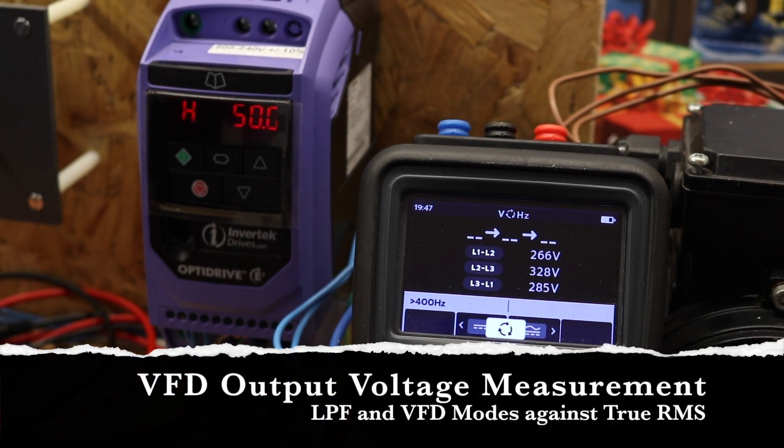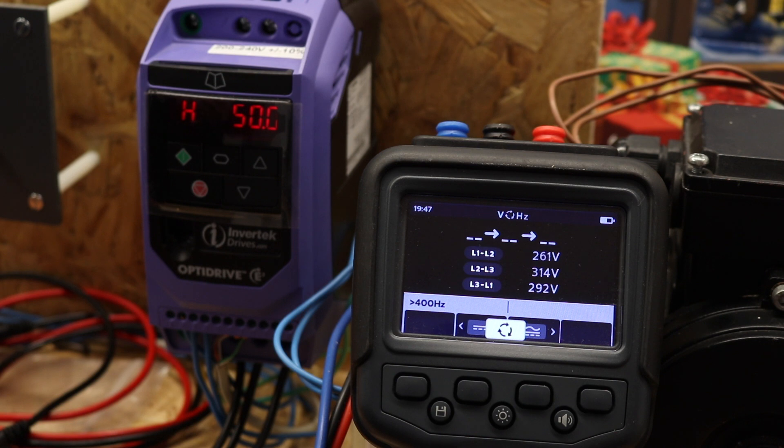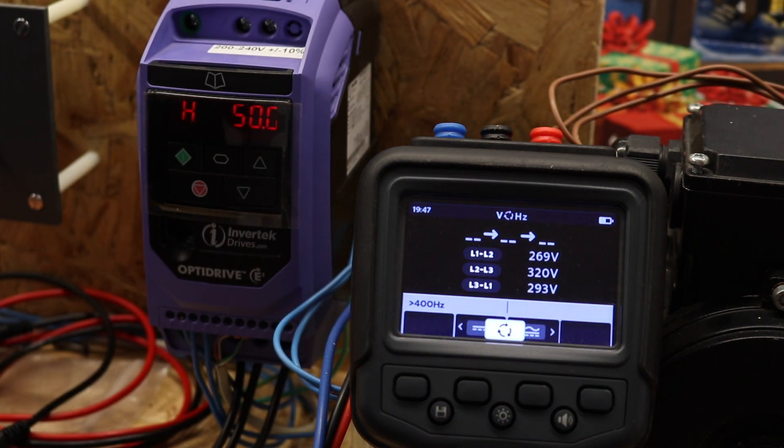Welcome back to the channel. In the last video I did the firmware upgrade on the MTR-105 and criticised it a little bit for not being able to measure the voltage output on an inverter. Here with the little Invertek unit and the MTR-105 in three-phase voltage mode, you can see the voltage is jumping around — it should be around 220 volts and the frequency should be at 50 Hz, but it's greater than 400 Hz and the voltage is going all over the place.